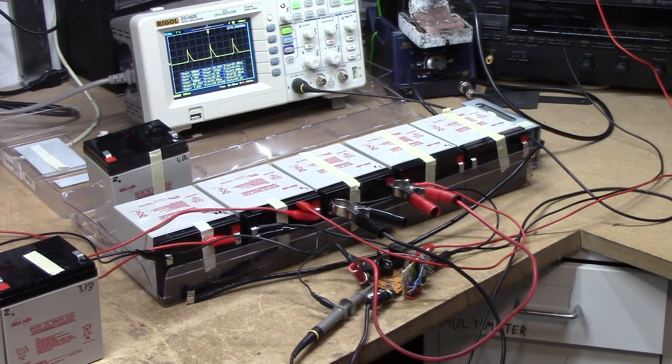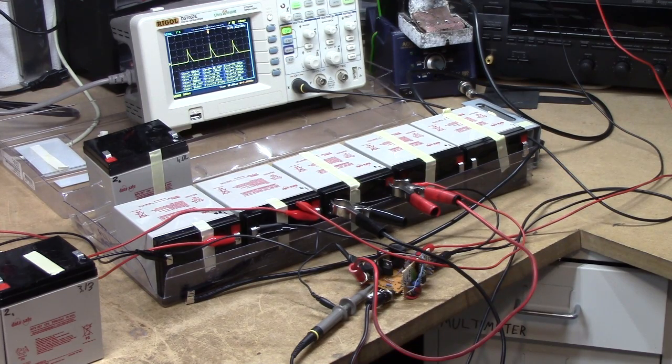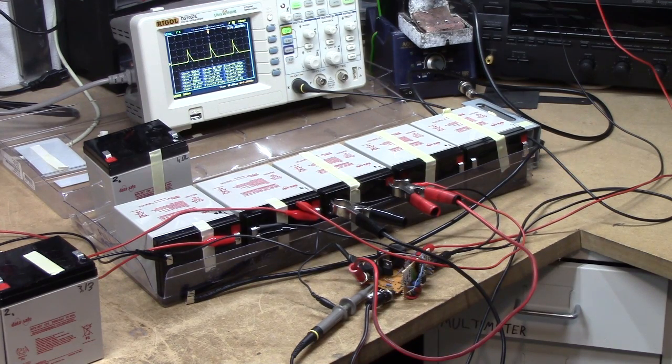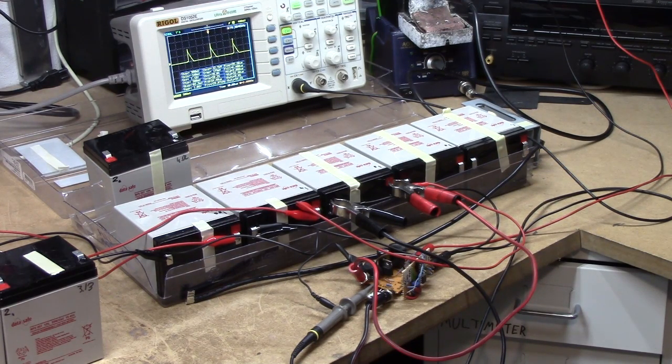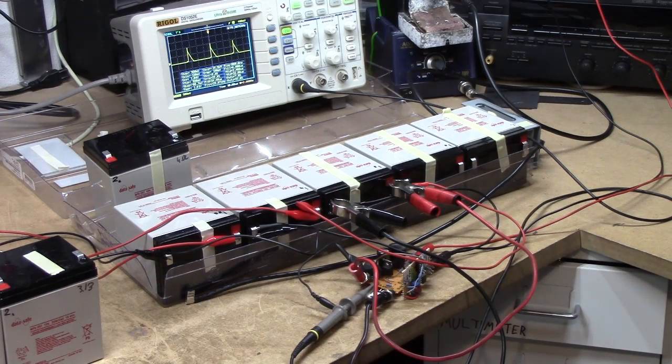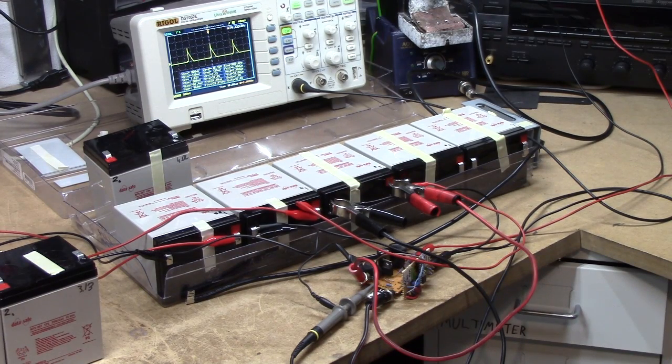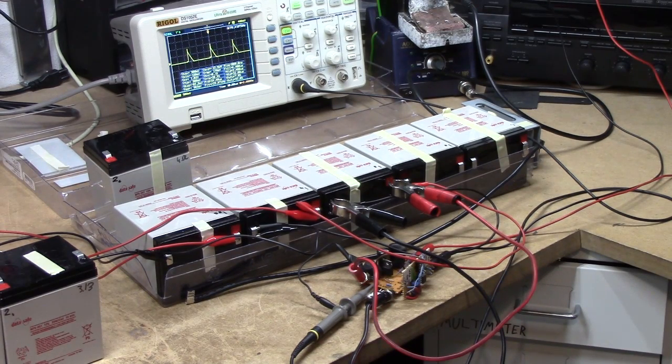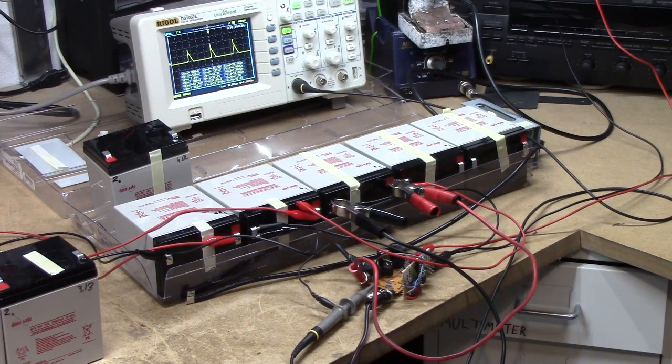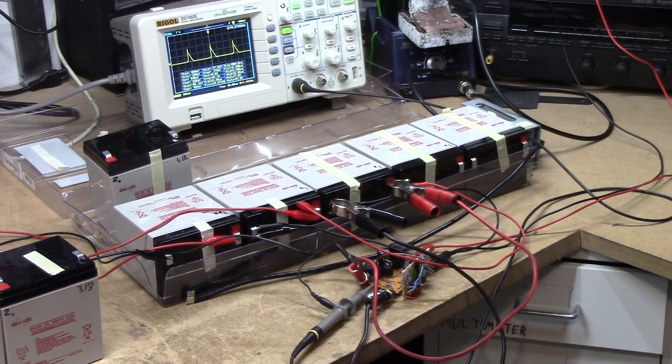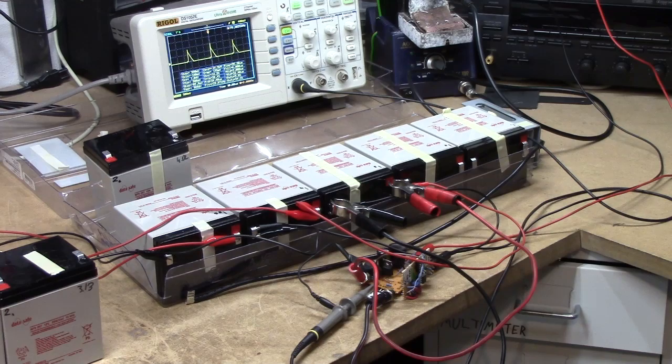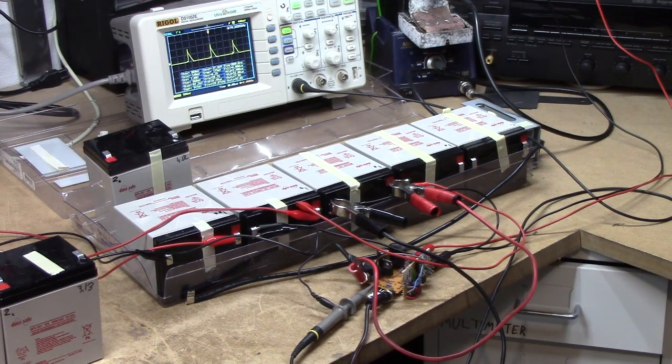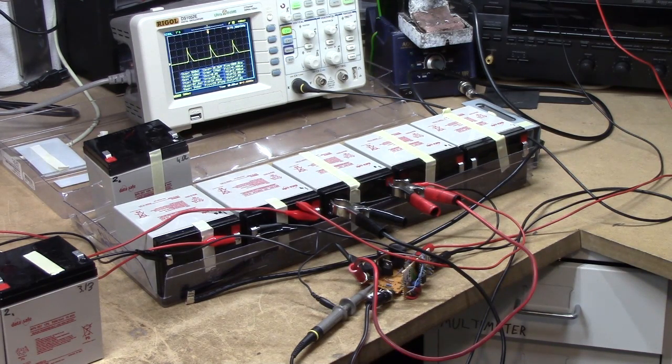The point of this is to allow the battery to absorb current at a high voltage without having to put high DC voltage constantly across the battery, which, as I'm sure a lot of you know, will cause the battery to expel its electrolyte in a rather violent manner, causing the battery to fail absolutely and without recourse.